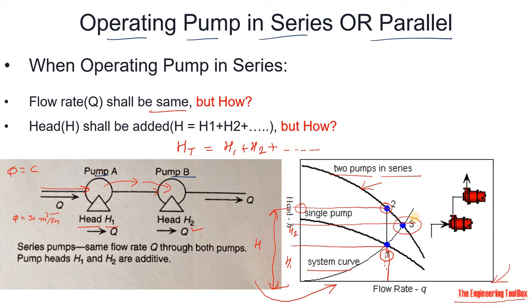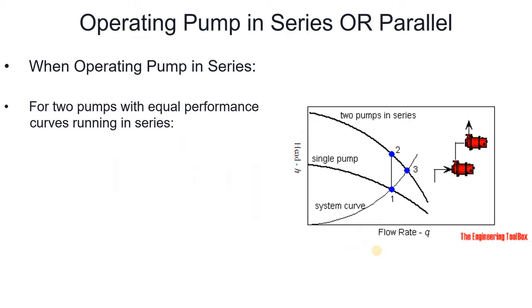Centrifugal pumps in series are used to overcome larger system head losses than one pump can handle. For example, if using only one pump results in too much head loss, operating multiple pumps in series allows you to overcome that larger system head loss. You can see on the graph how the operating point shifts when two pumps run in series compared to a single pump.